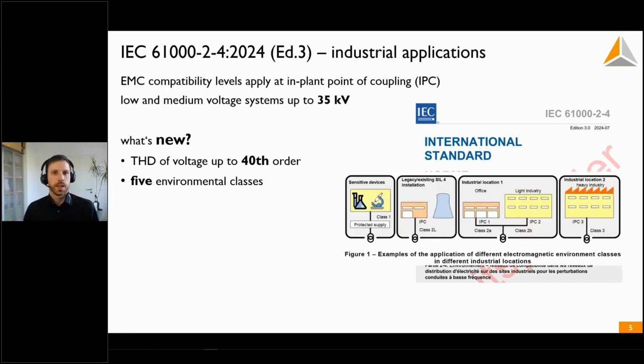The edition 3 has 5 classes by now. So class 1 is the same as before. Class 2L, L stands for legacy. It's the same as in the previous edition. And what's new? Class 2A and B. Now they distinguish between office environment and light industry environment. In most of the cases, the limit values are similar, but not every limit value. And as in the previous edition, class 3 for heavy industry. And I'm going to talk about these on the next slide.